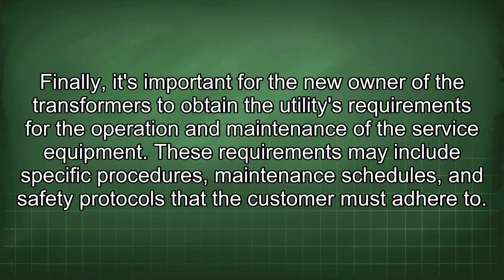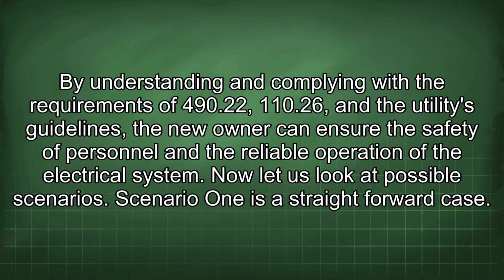110.26. Finally, it's important for the new owner of the transformers to obtain the utility's requirements for the operation and maintenance of the service equipment. These requirements may include specific procedures, maintenance schedules, and safety protocols that the customer must adhere to. By understanding and complying with the requirements of 490.22, 110.26, and the utility's guidelines, the new owner can ensure the safety of personnel and the reliable operation of the electrical system.